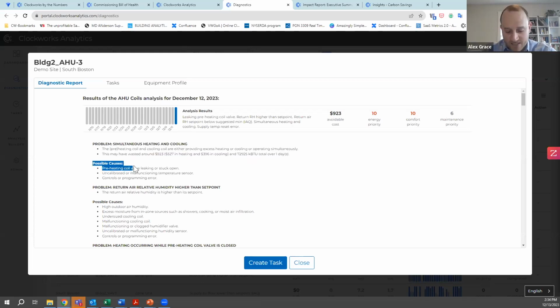This list of possible causes is not static—it's actually dynamic. So it's about getting to those issues and really saying, where do I start as a technician? Well, let's start with that valve and see if it's leaking or stuck. Now, it's not always the case that the preheat coil valve leaking is the first possible cause of simultaneous heating.